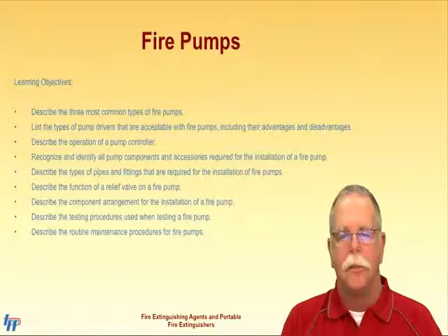A pump installation's components and accessories consist of piping and fittings, relief valves, circulation relief valves, test equipment, pressure maintenance pumps, and gauges. Fire pumps should be thoroughly tested when they are installed and should be regularly inspected, maintained, and service tested thereafter by qualified personnel.